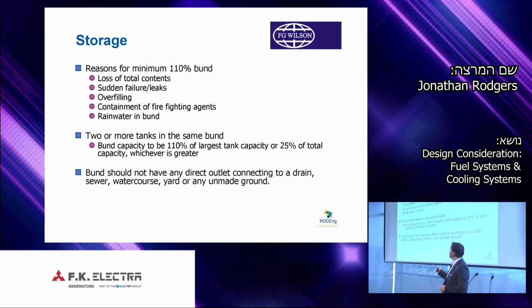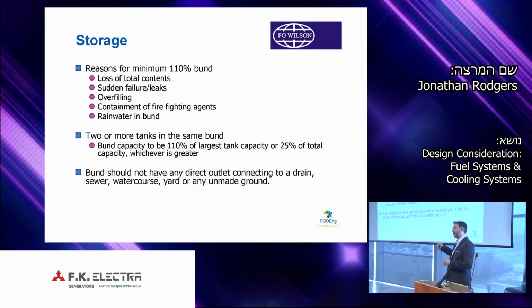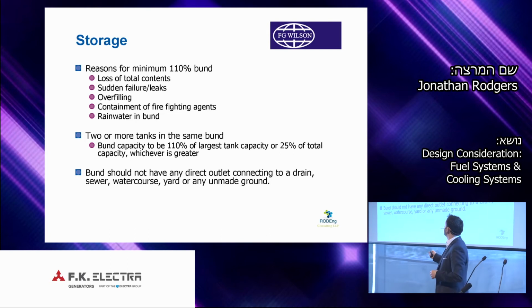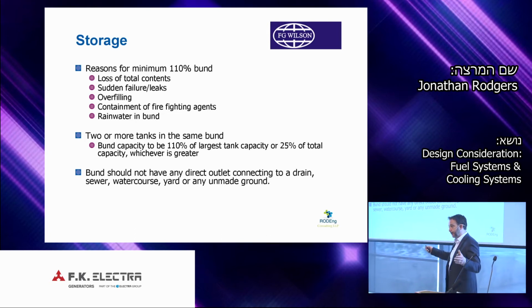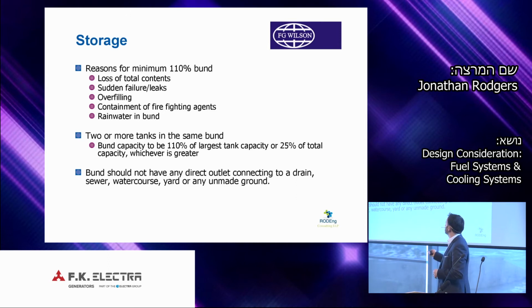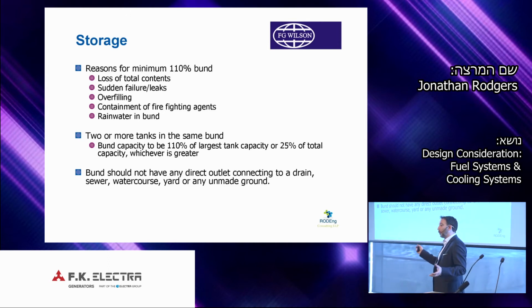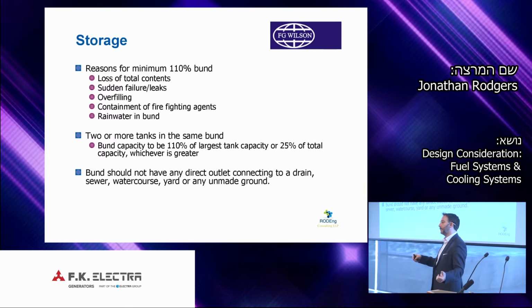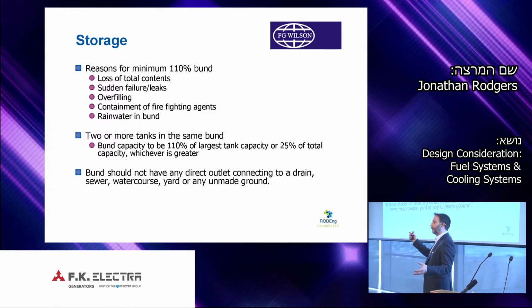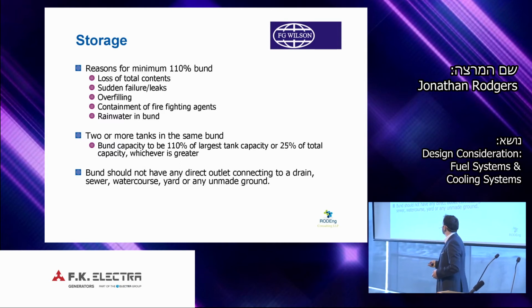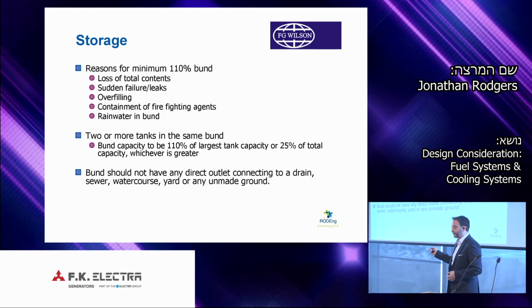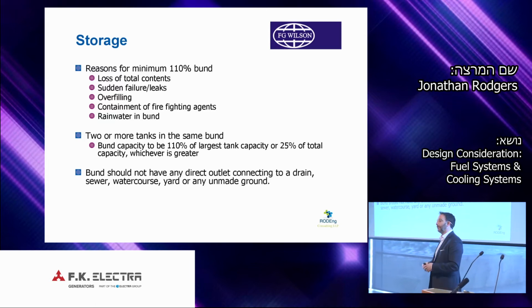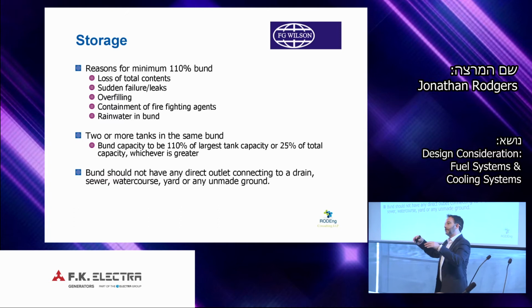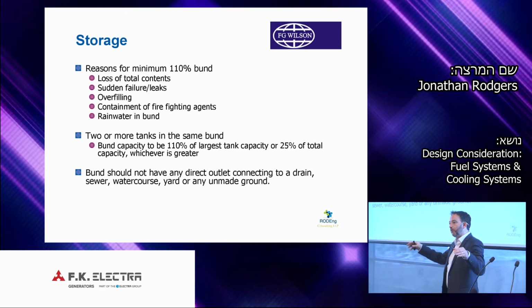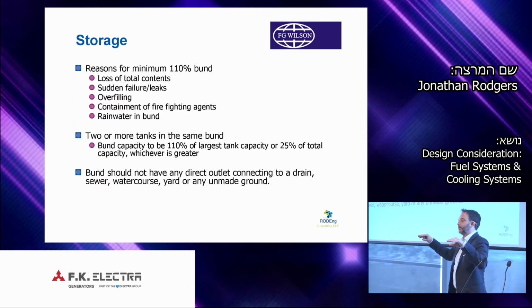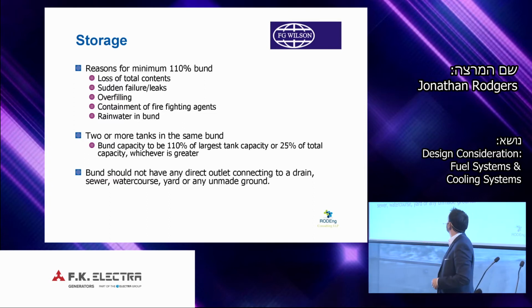Here's a summary of a number of points that need to be considered and the relative reasons. So the bund is bigger than the tank, so it can take all of the volume if the tank fractures or leaks. If there's an overfill of the tank with an alarm to signal overfill, the time delay to stop from an alarm means you need to increase the volume. If there is fire stopping in a tank room or fire protection that is injected into a tank room, that volume needs to be considered in the volume of the bund. So that's why we have to have a greater volume.